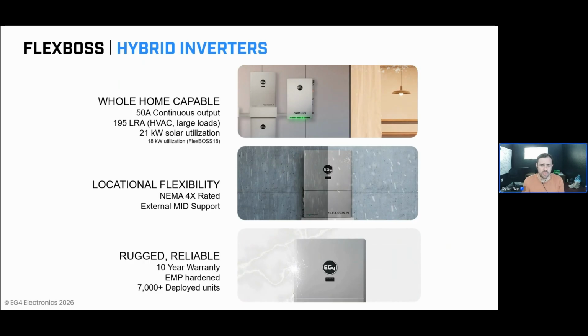But I think first and foremost, you really start to look at what your inverter is capable of delivering for you in the context of home backup and home power delivery. And the FlexBOSS is a whole home capable inverter for most modern US residences. Just for some background, when I say that, most average homes in the US, and you can see this across numerous studies, the one I've most recently been looking at was put forth by UC Berkeley's Energy Lab. Most average residents in the US are going to use 40 amps or less at their maximum demand moments. The 50 amp continuous output of the FlexBOSS 21 is more than enough power to reliably power any home that has a typical max demand of 40 amps with some additional headroom.